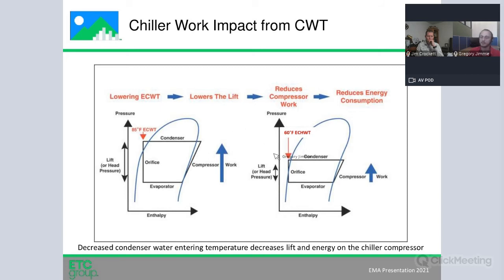So the second component of this is going to be getting into the condensing water side. A similar idea here is that we want to bring the top down, or bring the ceiling down, of the enthalpy pressure diagram. So in this example, we are going from maybe 85 degrees to say 60 degrees. A lot of chillers in, say, Arizona are going to be designed for like an 85 degree entering and a 95 degree leaving condensing water temperature. So a lot of times you'll see chiller plants set up where they're just controlling to that design point. So it only ever controls the condensing water down to 85 degrees.